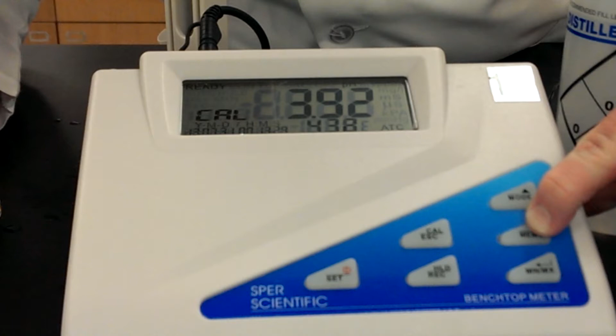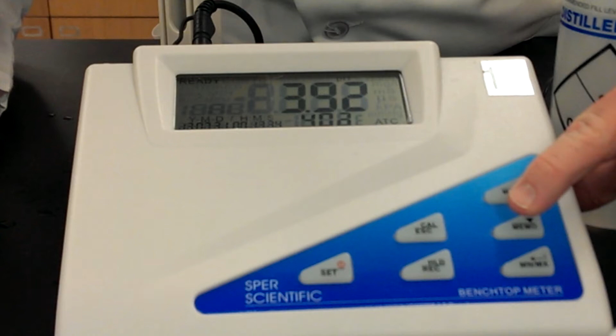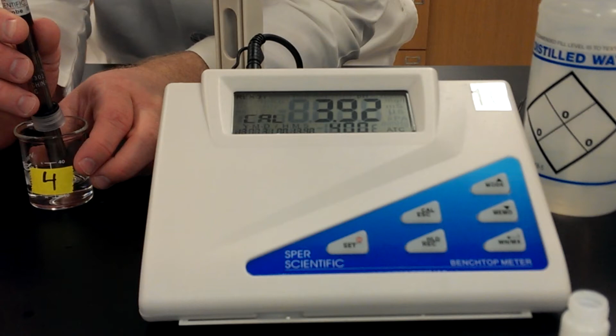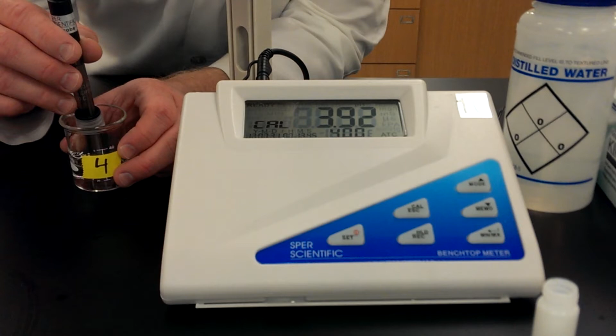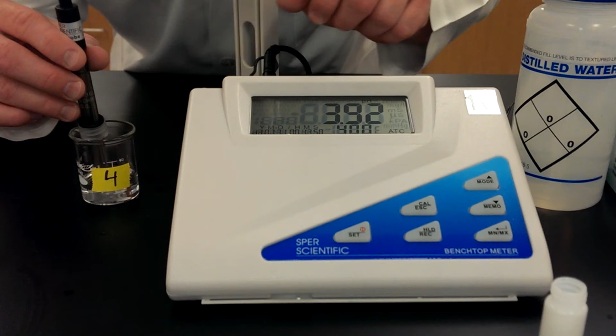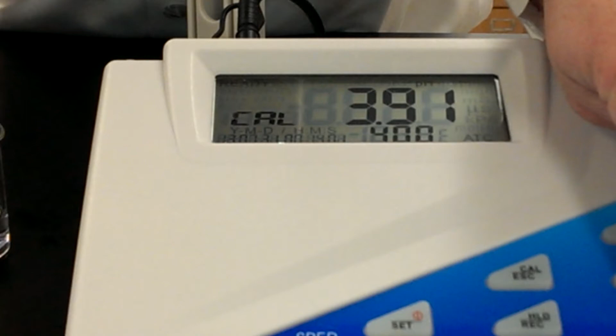Now we're using a 4.0, so we're going to have to change that number now. We're going to do that by pressing the down arrow with this button right here, and we're going to hold it until that number goes down to 4.0. Alright, 4.0. Now, once we're on 4.0, I'm going to swirl around the electrode in the solution until you see the word ready at the top corner of the screen here. And once you see that, that tells you that that's actually what the pH meter is reading, and we can now calibrate it. We do that by pushing the enter button.